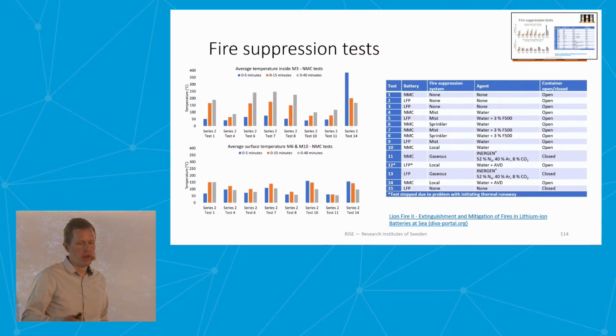So when talking about suppressing battery fires, you often talk about cooling, but that's important when it's tightly packed, and for propagation, for example, inside a module. But if you have some airspace between the modules, the flames will probably have much greater influence.